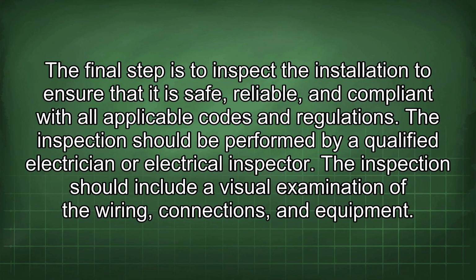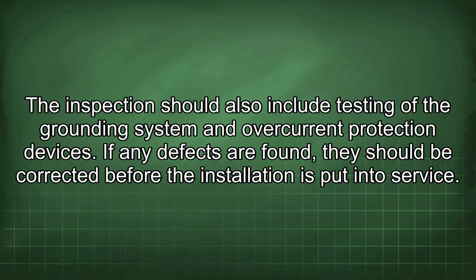The final step is to inspect the installation to ensure that it is safe, reliable, and compliant with all applicable codes and regulations. The inspection should be performed by a qualified electrician or electrical inspector. The inspection should include a visual examination of the wiring, connections, and equipment. The inspection should also include testing of the grounding system and overcurrent protection devices. If any defects are found, they should be corrected before the installation is put into service.